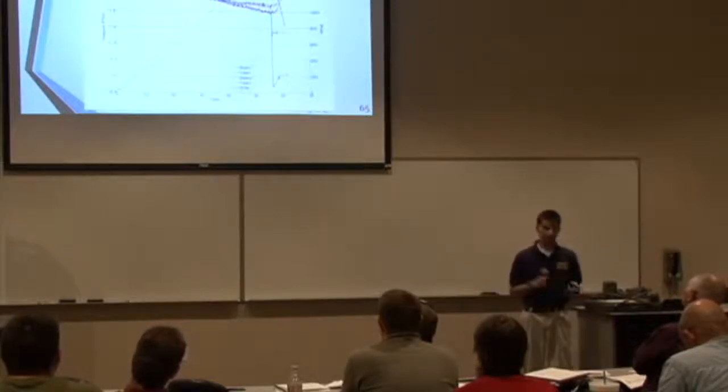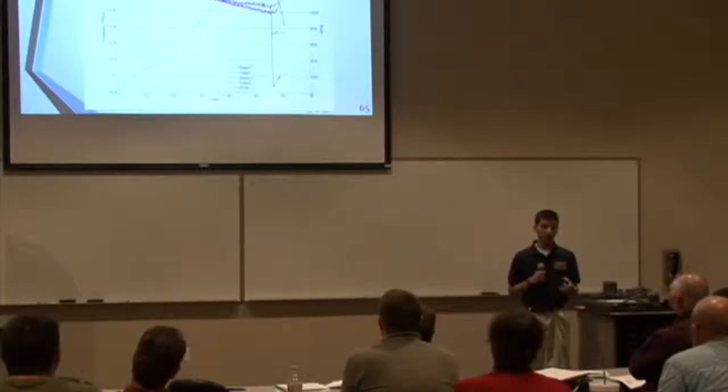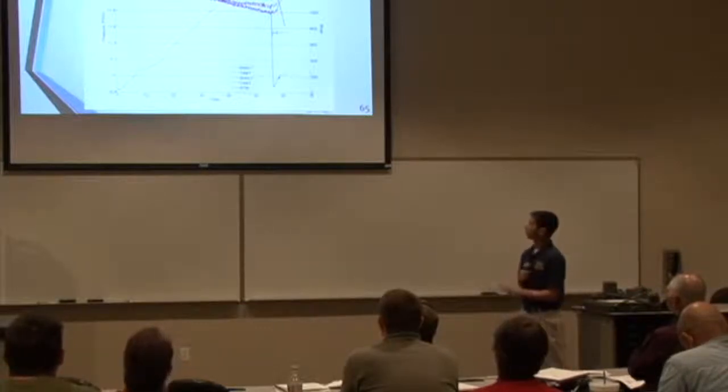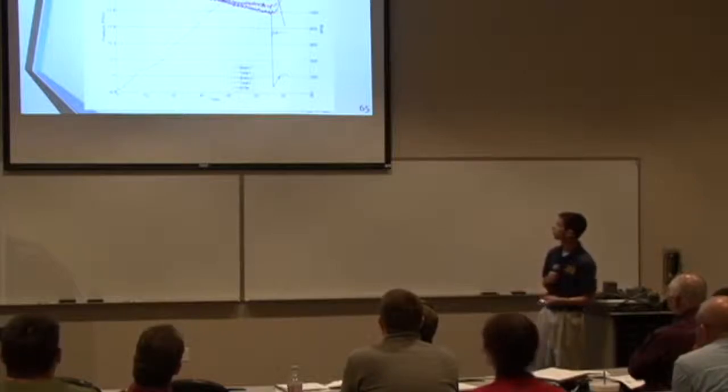So then we decided that we would try to shoot for an 1800 RPM test. As you can see behind me, we didn't actually make it there. We had a failure at just under 1600 RPM, and as the standard protocol, with the failure, we brought IRIS back down to a stop. So you can easily see from this graph and the one I'll show in a few slides that as the RPM increased, there is a definite drop in pressure.